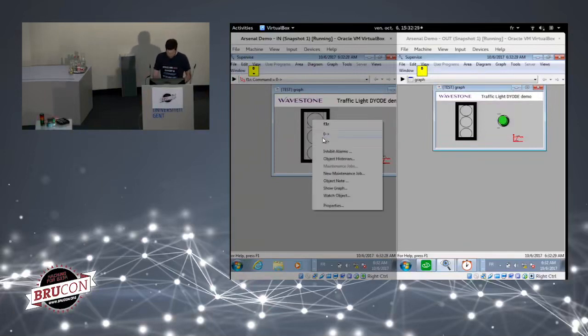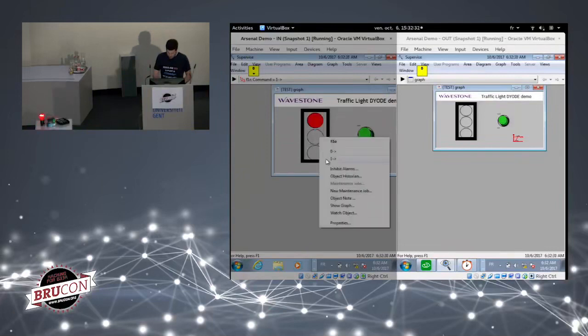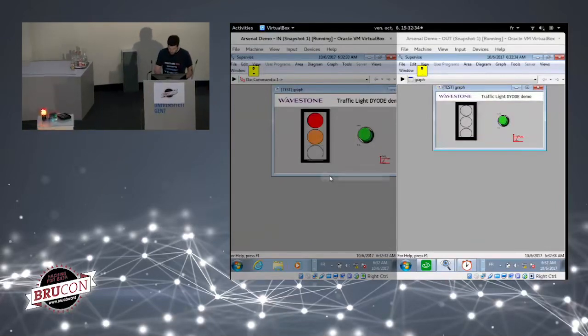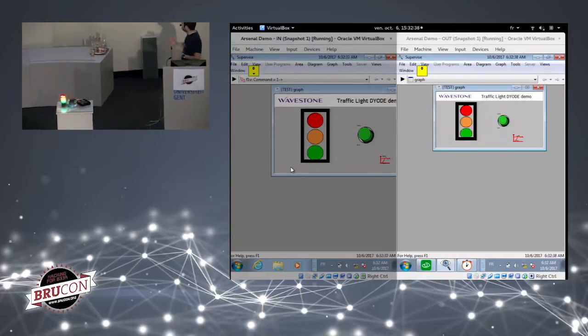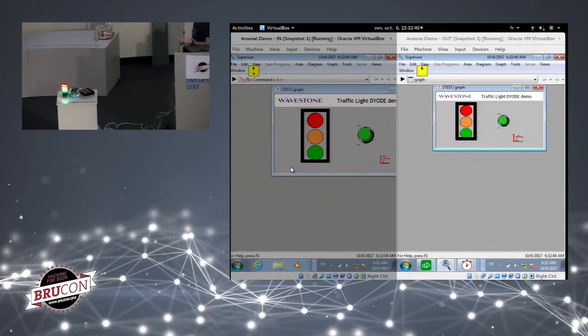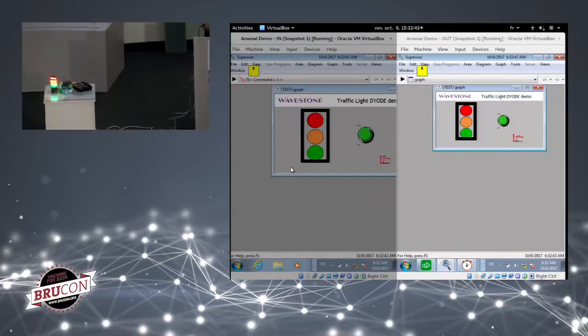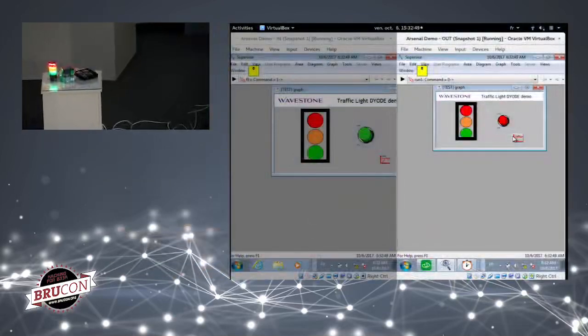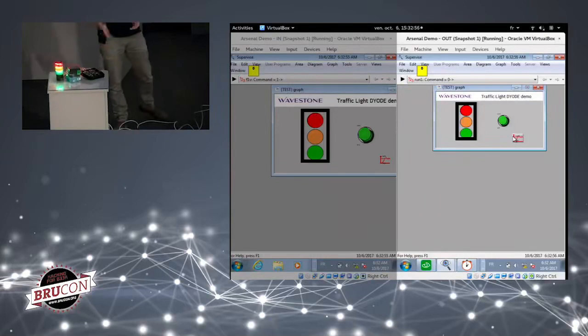So what should happen is that I can actually switch some lights on and off. And yes, with a few seconds of delay, you can see that on the right side, the information is copied. Since I do not want to cheat, I'm going to show you that if here I try to perform an action, of course, it's not working, because it's trying to send data to the PLC, but actually it's sending data to the diode, so it does not go through.